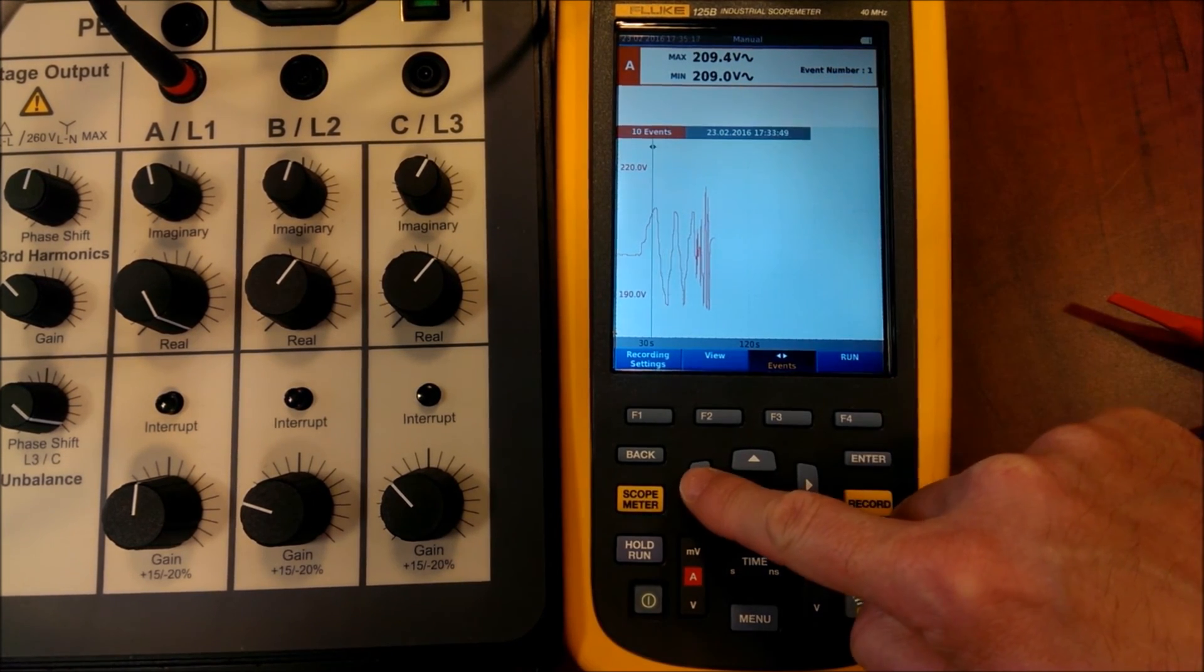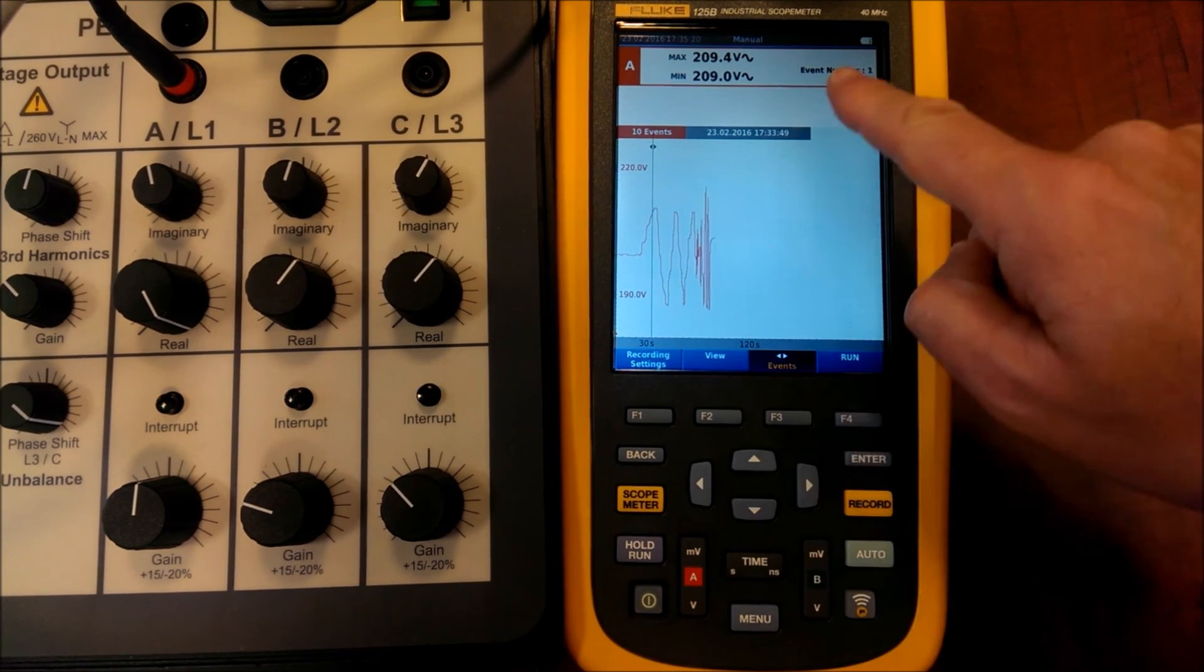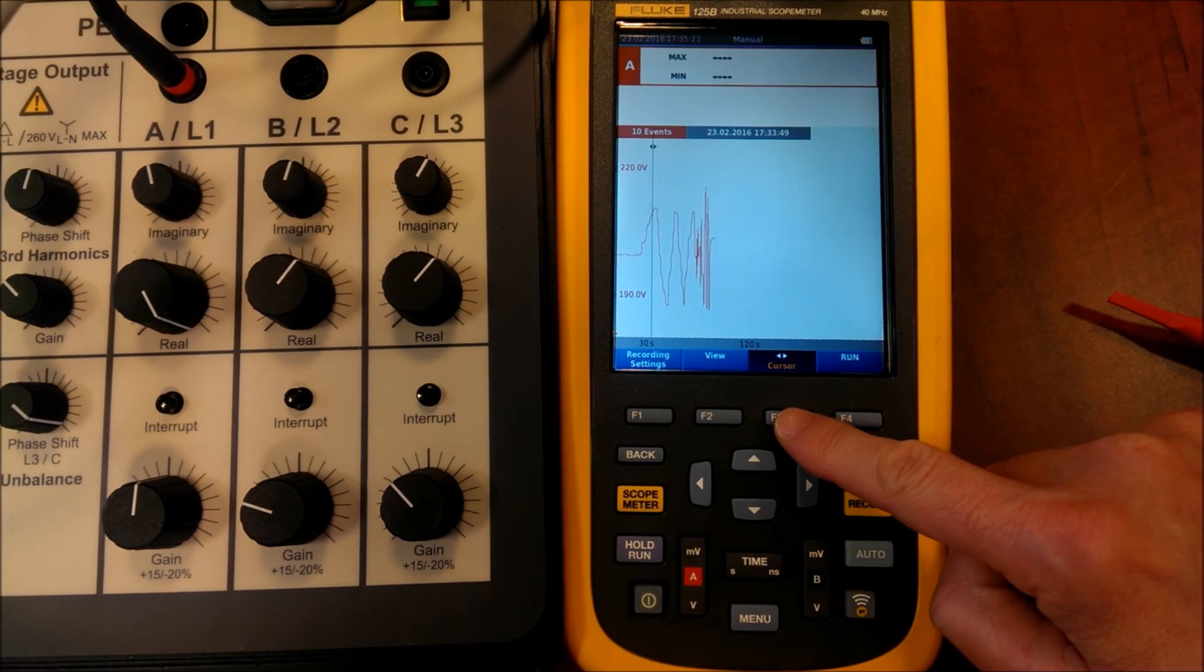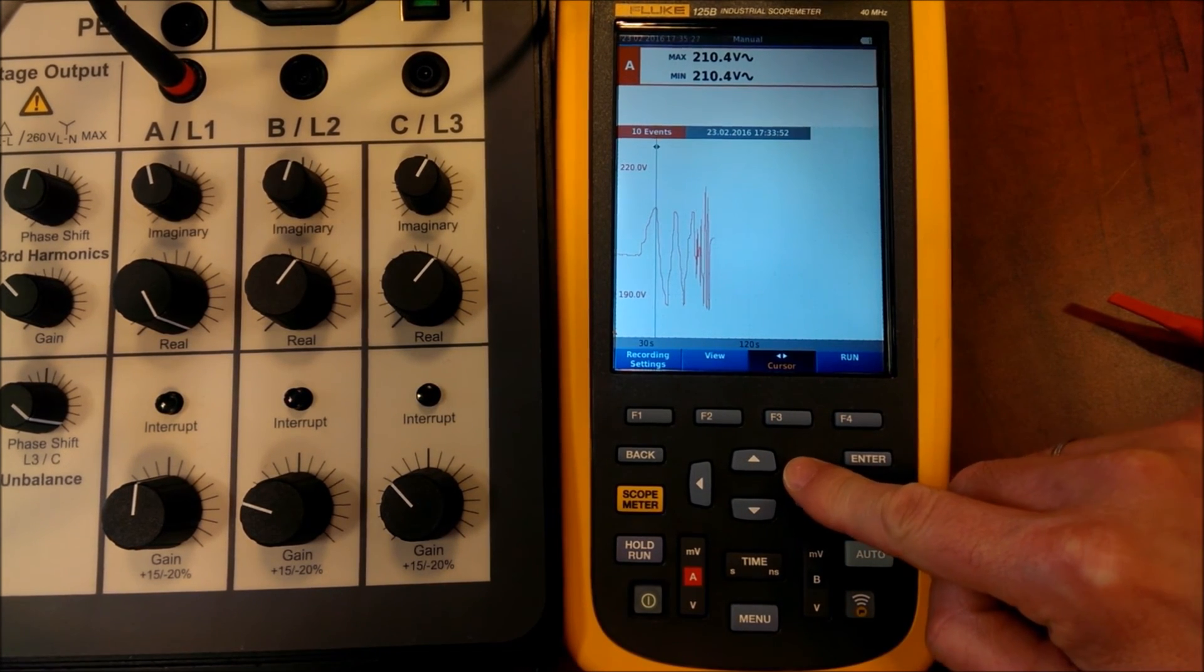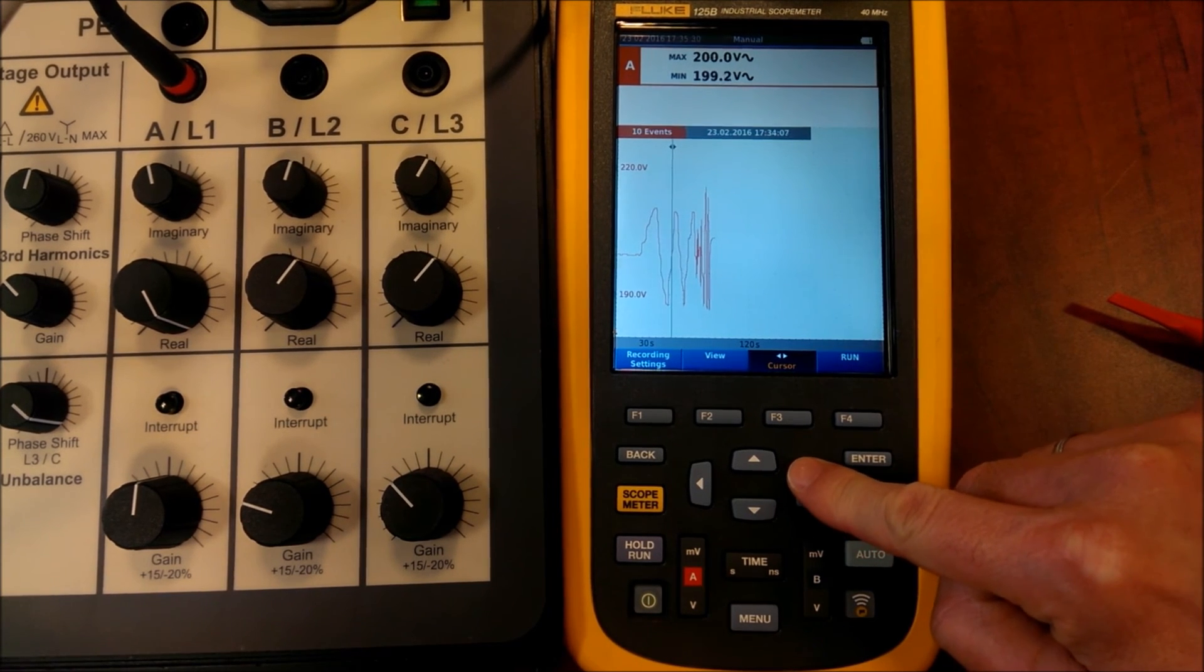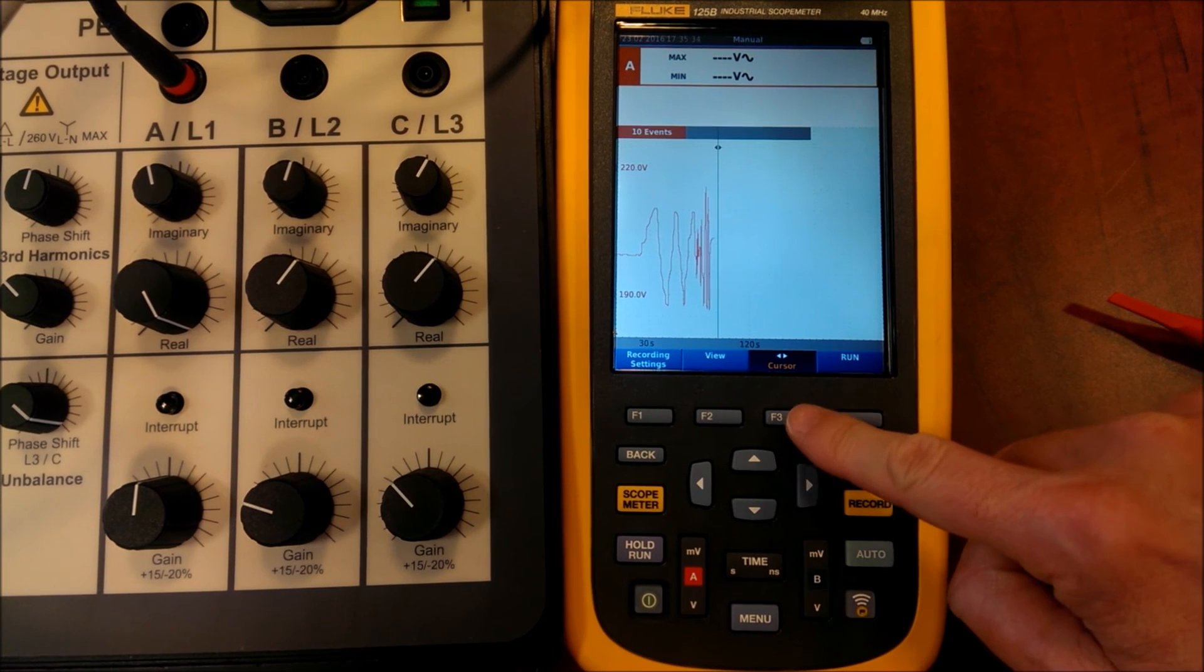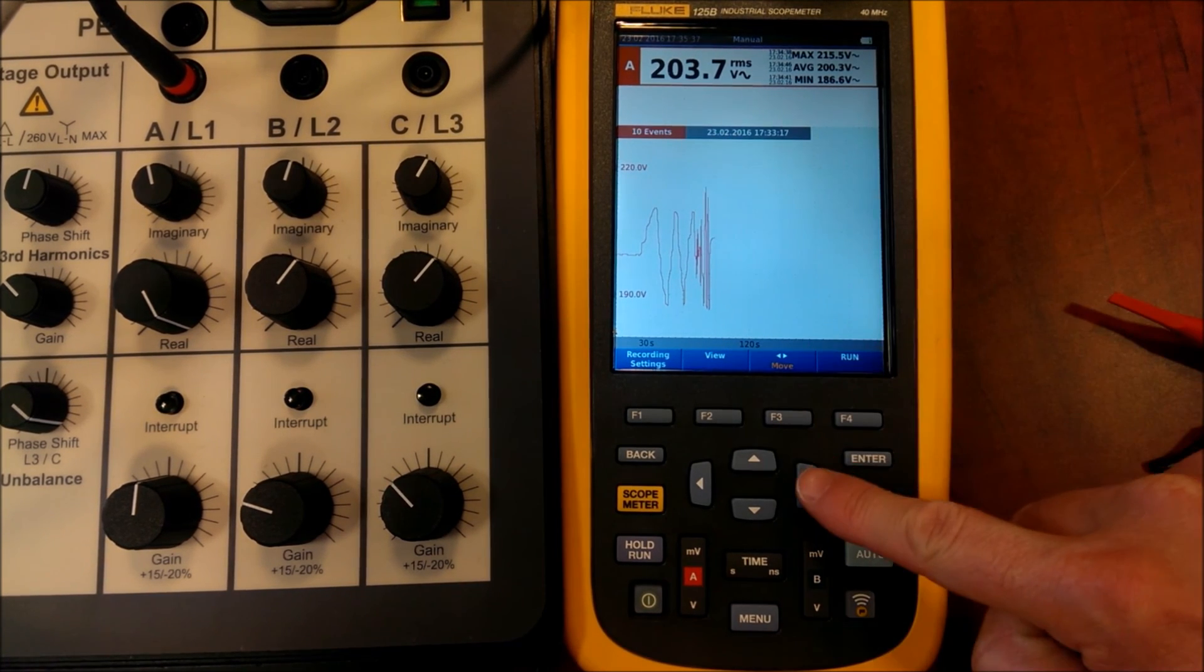This event function is very useful. In a very simple way we can define the upper and lower limits. So that the oscilloscope will capture the events providing information about when that event has happened, and the maximum and minimum values of the voltage for the averaging period when the event has happened.